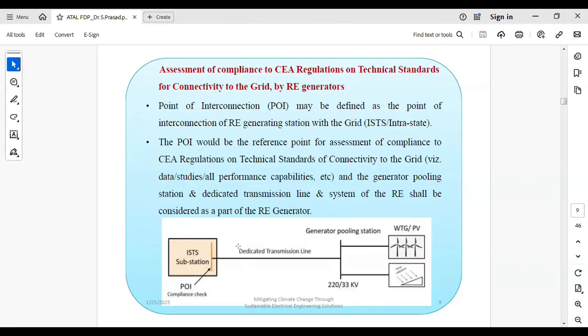In this figure, you can see the ISTS substation and dedicated transmission line, then the generating pooling station. That means the power evacuation will be taking place at the PoI point. That means how much power you are generating using solar or wind will be evacuated at the interconnection point through transmission lines. The transmission line and generating pooling stations up to this part will come under the RE generators. And at the point of interconnection, we have to fulfill all the requirements according to the Indian grid code.